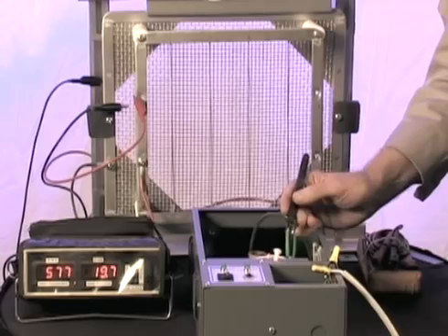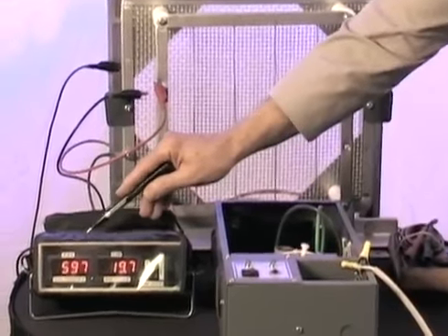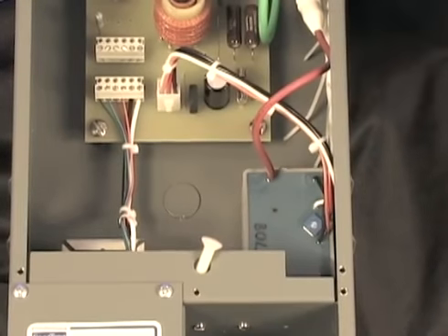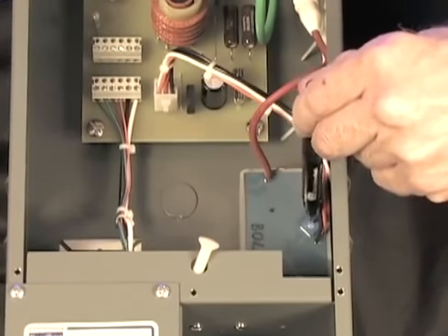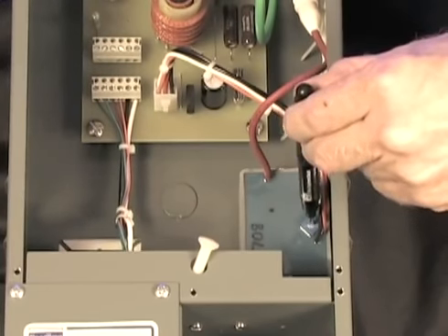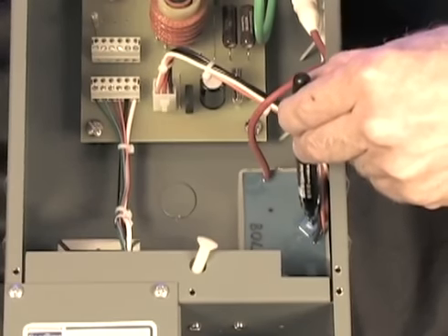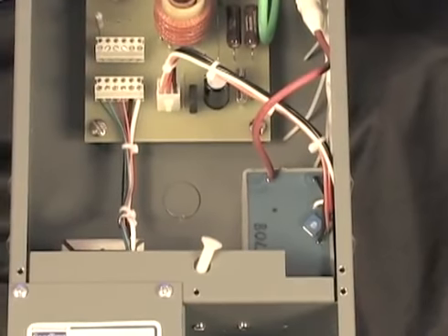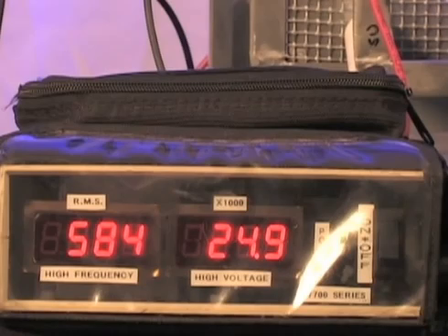With our test kit hooked up to the screens, we can see that our high voltage is actually low and our high frequency is actually okay. So what we need to do is adjust the high voltage up. There's a small potentiometer encapsulated on the high voltage module. And if you look down in, there's a slot where you can get your screwdriver. And if you turn the screw, you can actually get the high voltage to come up to the level you want. 24.9 is a nominal position, and performance has been restored to the CosaTron system.